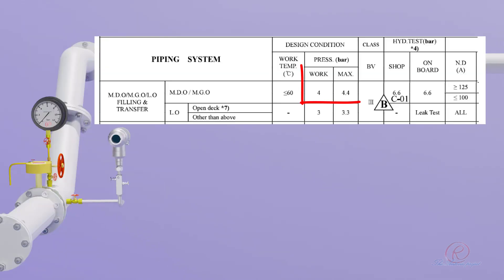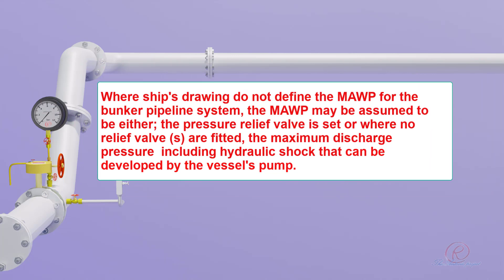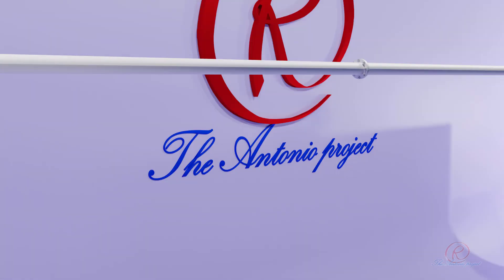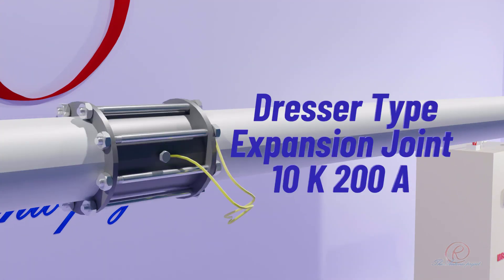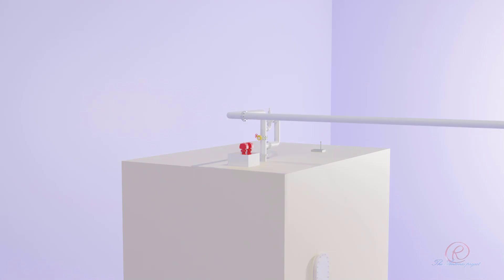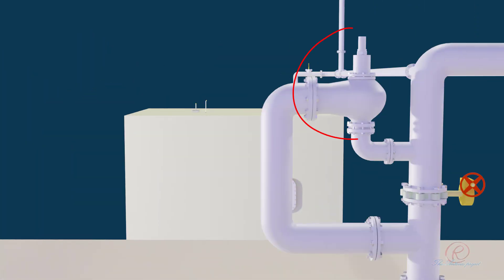Normally, the MAWP or Maximum Allowable Working Pressure is stated on the piping diagram. Where ship's drawings do not define the MAWP for the bunker pipeline system, the MAWP may be assumed to be either the pressure at which the relief valve is set, or where no relief valves are fitted, the maximum discharge pressure including hydraulic shock that can be developed by the vessel's pump. Safety valve setting pressure is 4.4 bar.